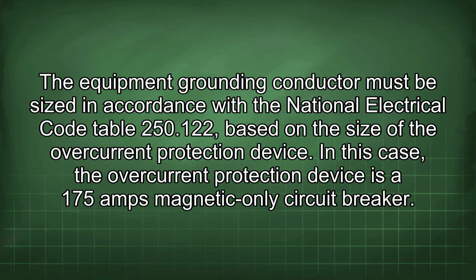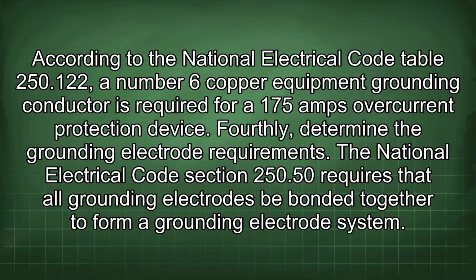Thirdly, calculate the minimum size of the equipment grounding conductor. The equipment grounding conductor must be sized in accordance with the National Electrical Code Table 250.122, based on the size of the overcurrent protection device. In this case, the overcurrent protection device is a 175 amps magnetic-only circuit breaker. According to the National Electrical Code Table 250.122, a number 6 copper equipment grounding conductor is required for a 175 amps overcurrent protection device. Fourthly, determine the grounding electrode requirements.